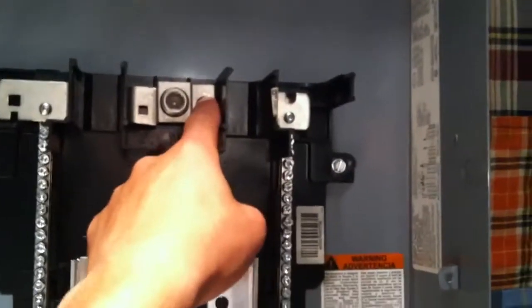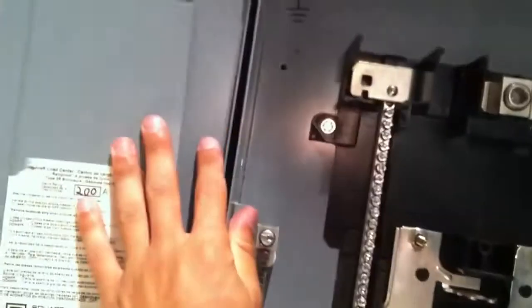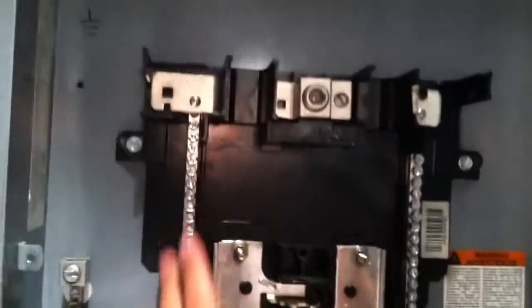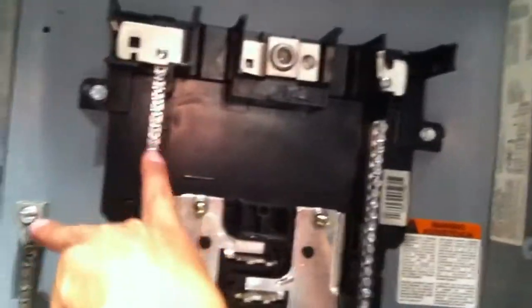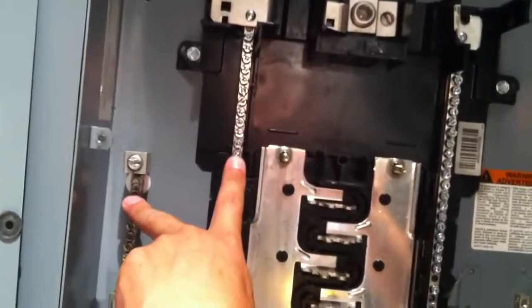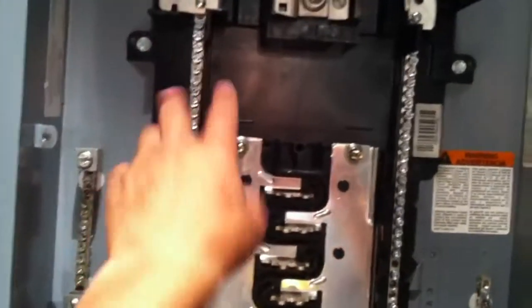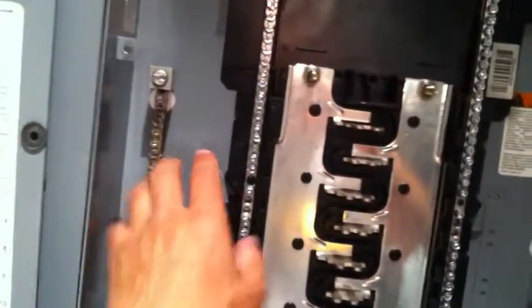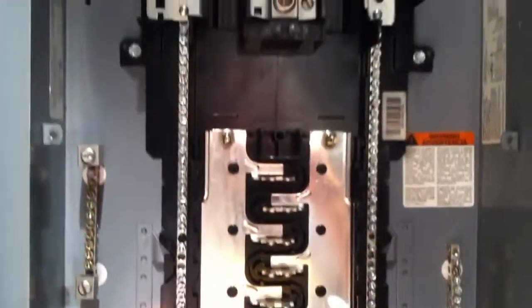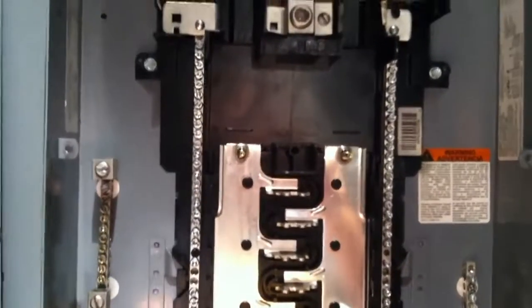I didn't put my ground wire in there. I put my ground wire in here. It's grounded to the case. The neutrals are all separated from the grounds. The grounds and the neutrals are not touching. Okay, they're totally separate. That's how it is in California. Sub panels are separate, main panels all the same. You don't have to have a ground strip on the side, you don't have to have this crap. It's all the same. Why they do that? It's weird. I don't know.